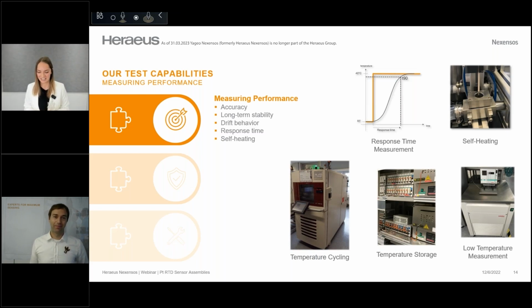You will also find the response time and the self-heating as characteristics on our data sheet. And actually both are measured in the same equipment that you can see on the top right for the self-heating. So let's talk about the response time. That's the time a sensor needs to detect the temperature. It's actually very decisive for a sensor assembly. And the sensor needs to be energized, therefore a slight self-heating could occur. So with this test setup, we can determine both. All right, next slide, please.